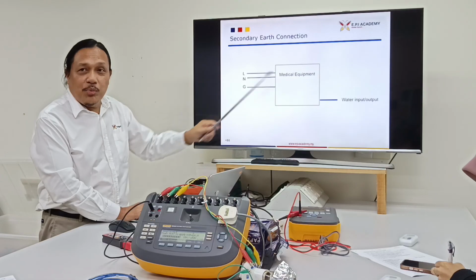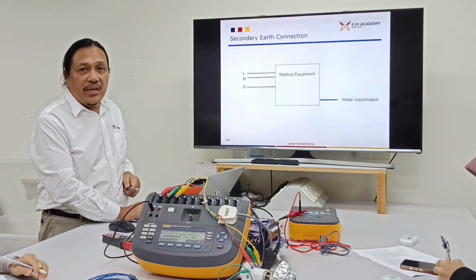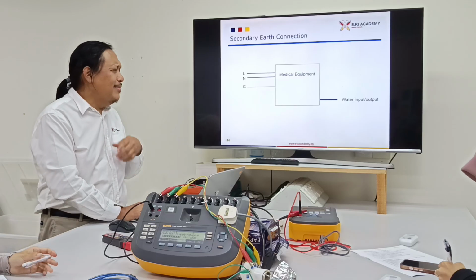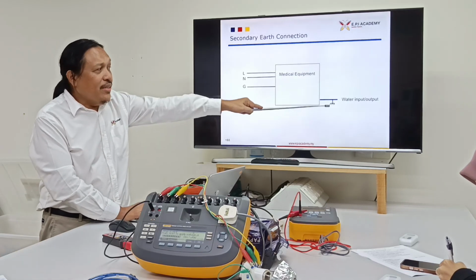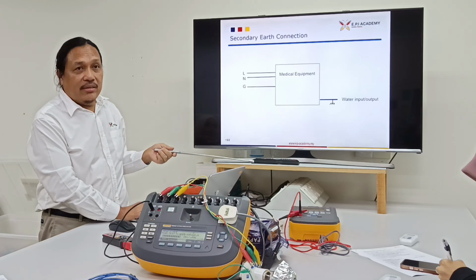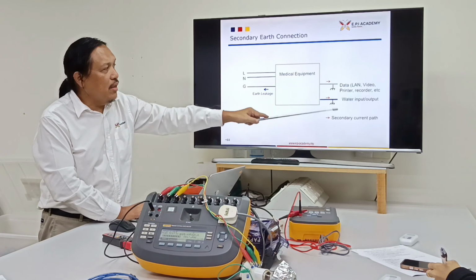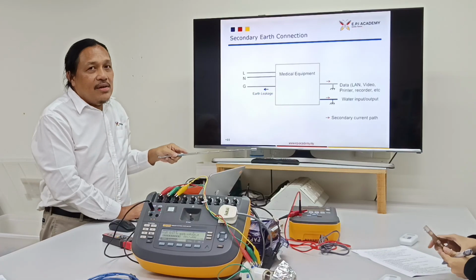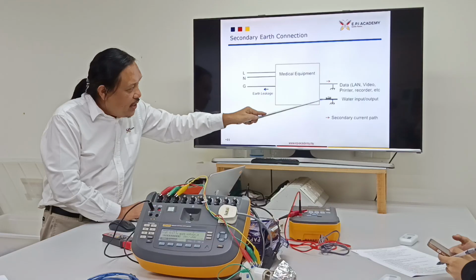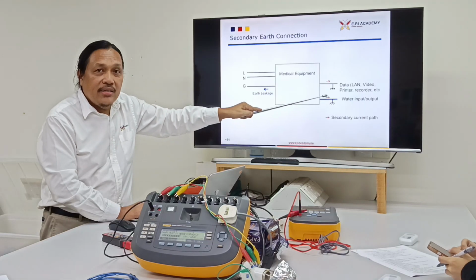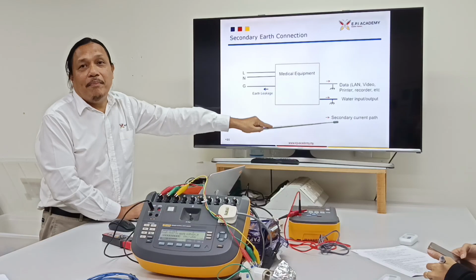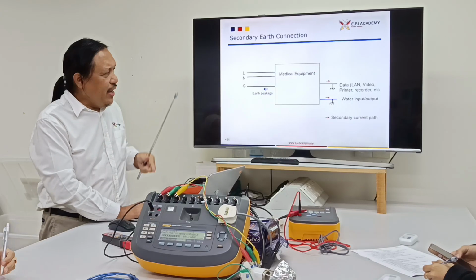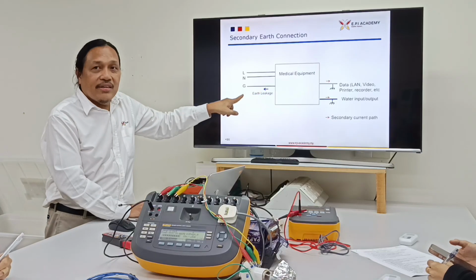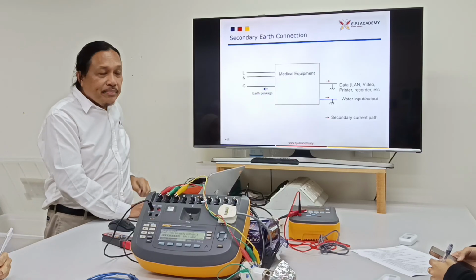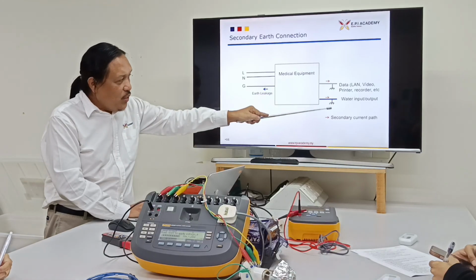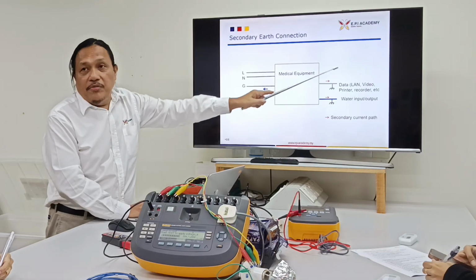Some equipment has water input, which makes it not portable anymore. And that water, of course, is connected to ground, to earth. Some equipment has data connection, internet, printer. And of course, since these are connected to earth, leakage can also flow there. This is called the secondary path of leakage current, or secondary leakage. This is the earth leakage, by definition, to the power cord. Since this is connected to earth, this water and this leakage can flow there.